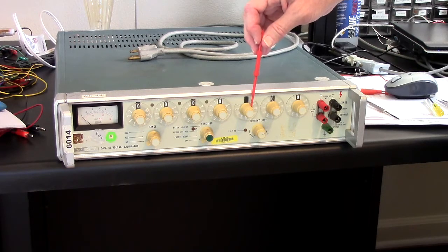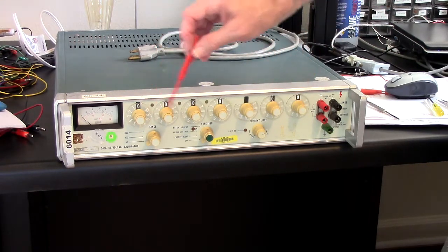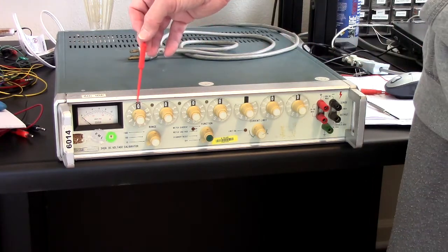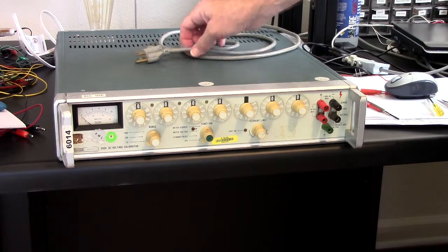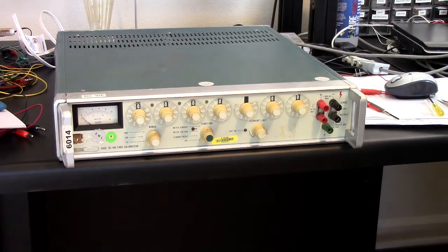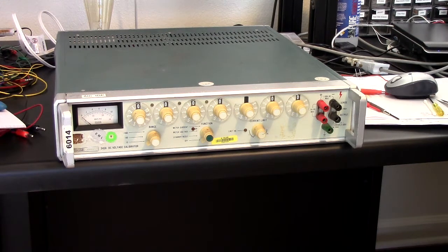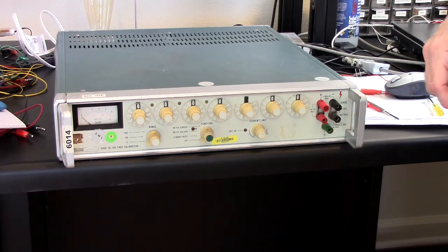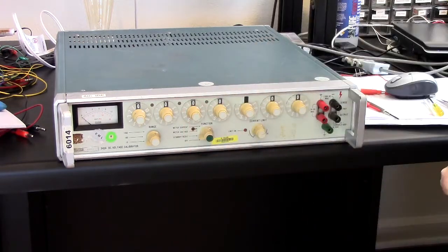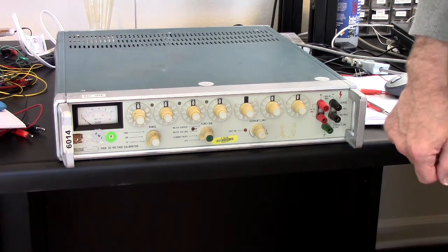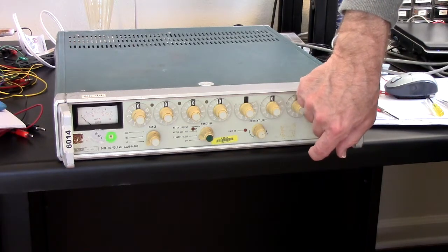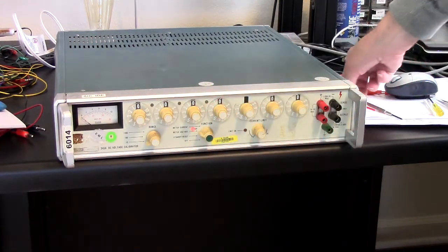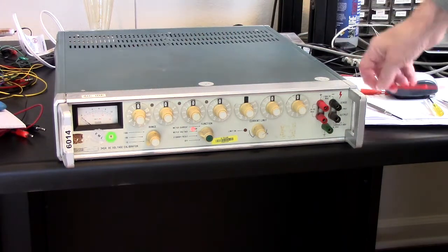What I can do on the broken dial is move it down to the last digit, because this is 7.5 digits, which means the highest order digit goes to 10. But let's plug it in and see what happens. Okay, plugged it in, and put it to standby, which did not appear to do anything. No lights came on. Well, that's a sign. We got a light there and a clunk from a relay. A light came on, which says on.